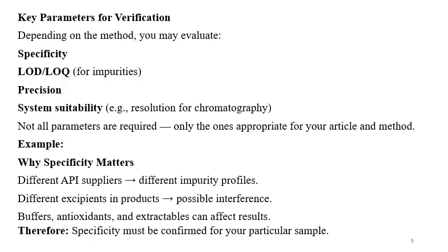Now coming to the key parameters for verification, because verification is not validation. Depending on the method, you can evaluate specificity, LOD, LOQ for impurities, precision, and system suitability, like resolution in chromatography. Not all parameters are required; only the ones appropriate for your article and the method need to be verified.